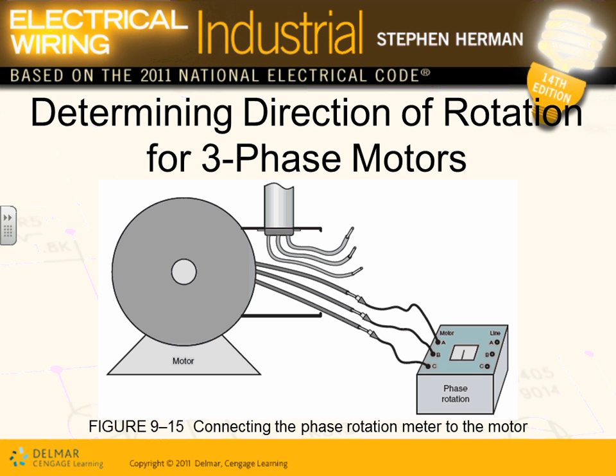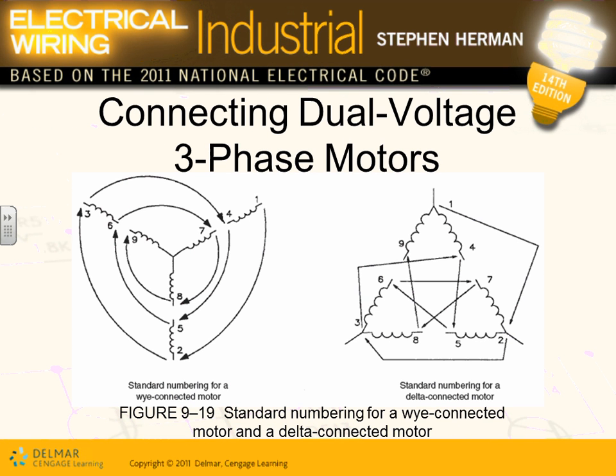If you're a project manager, again, we don't use this. That's for the designer, guys. But be aware that before you connect the machine to a line, you need to make sure that phase A, phase B, phase C is lining up. If you flip them, what happened? You rotate the machine, and it's going in the opposite direction. Bad news. So that's why they have this phase rotation meter that identifies the rotation of the equipment. Be aware of that.